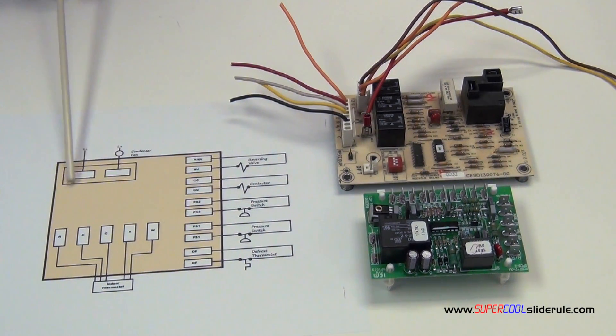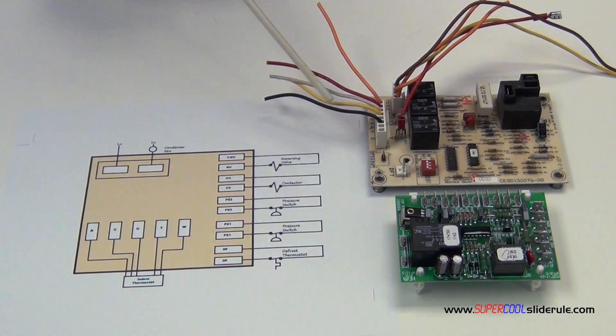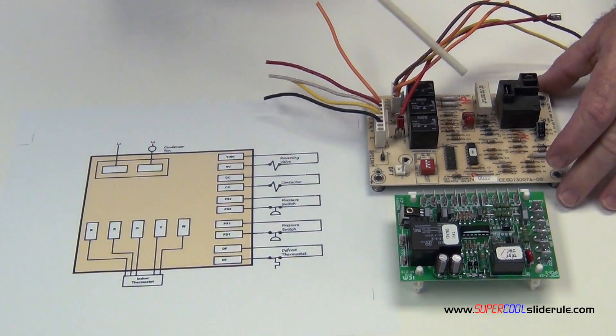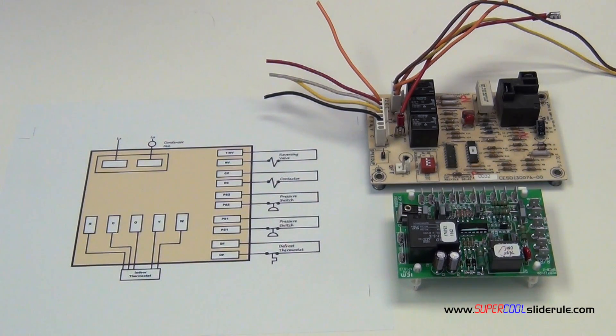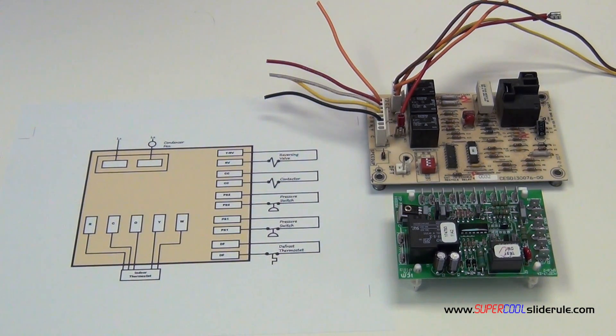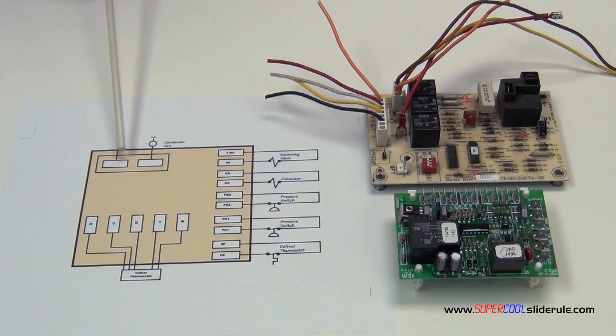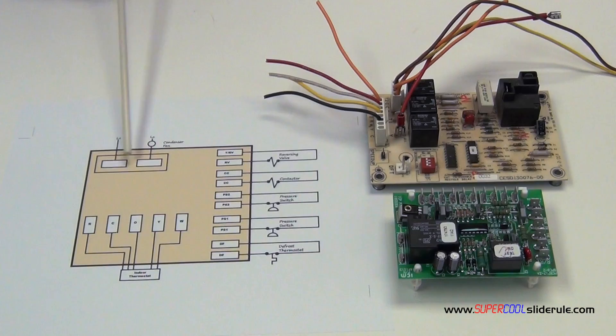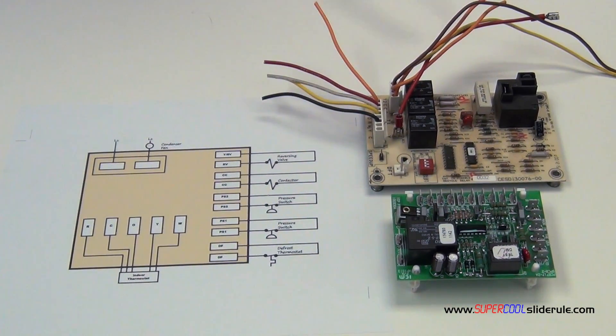The next thing we have is this right here. This is your condenser fan relay. On this unit it's right there, on this one it's here. What this does is controls the operation of the condenser fan. When the unit goes into defrost, this relay is not energized so the condenser fan does not run while the unit is defrosting. A lot of times technicians will forget that even on air conditioning, this relay must transfer the power from line one to line two through the condenser fan.